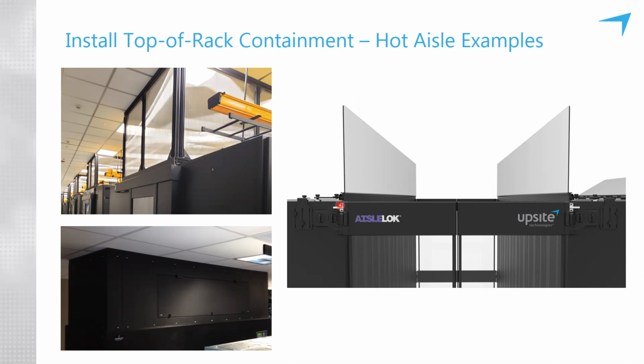On the right here, we see the Upsite AisleLok rack top baffles in a vertical configuration. So there are two different SKUs. One is angled, as I showed you for the cold aisle, and the other SKU is vertical, generally used for a hot aisle. But these can also be used for a cold aisle when there is overhead delivery, ducted supply onto, say, a slab environment, and you just need to create a higher rim for the bathtub on the cold aisle. But generally, the vertical baffles are used on a hot aisle, and they block the hot exhaust air from flowing right over the top of the cabinet into the cold aisle.